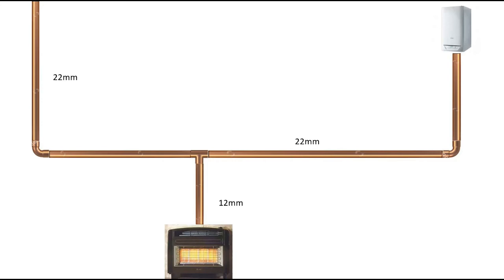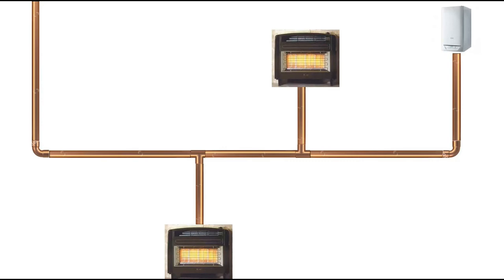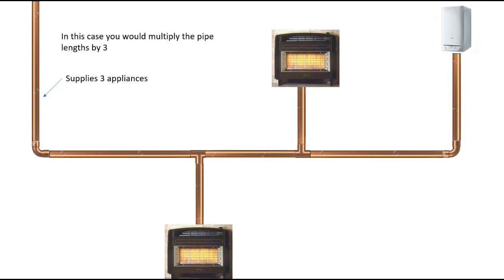If there were three appliances on the system, we simply take each pipe length — A to B, B to C, C to D, D to E — and multiply each by three. If there were four appliances, we multiply by four; five appliances, multiply by five. In this example, the first run A to B supplies three appliances because if you took it away none of them would get gas. The middle section only supplies two appliances, and the remaining two pipes only supply one appliance each. Pipe sizing made simple.